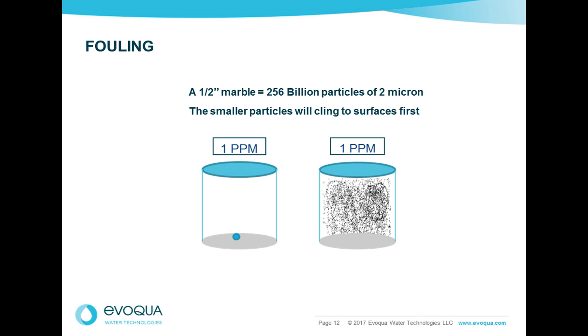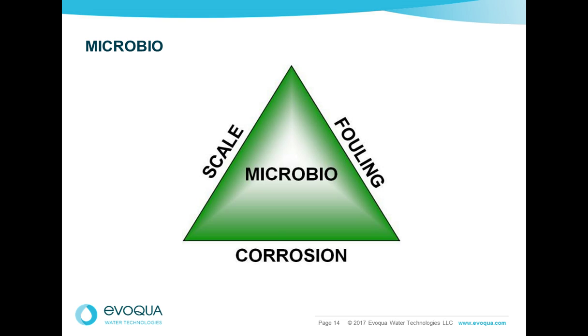The size of the particles also affects things. If you've got a half-inch marble in a system, you've got one particle. But if you disperse that same marble into 2-micron particles, you can have billions of them. So the big particles don't tend to cause a problem. They move through the system, get washed off, and don't stick to the tubes. But little particles stick to the tubes and form a film.